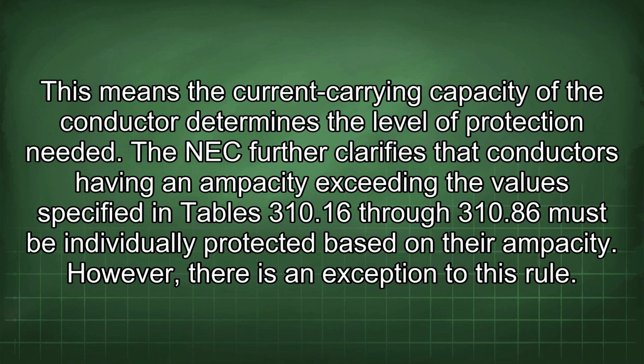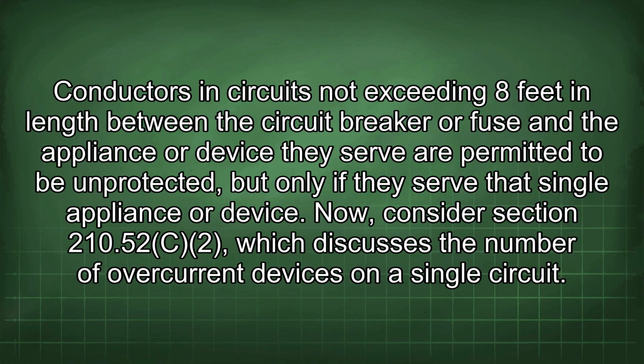The NEC further clarifies that conductors having an ampacity exceeding the value specified in Tables 310.16 through 310.86 must be individually protected based on their ampacity. However, there is an exception to this rule. Conductors in circuits not exceeding 8 feet in length between the circuit breaker or fuse and the appliance or device they serve are permitted to be unprotected, but only if they serve a single appliance or device.